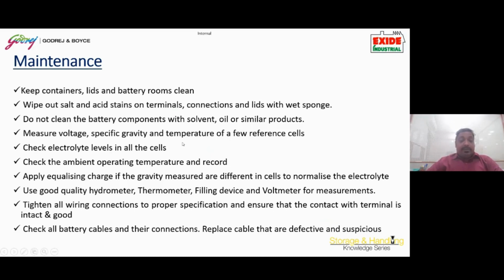The specific gravity, voltage and temperature of your reference cells should be measured periodically and noted down. The electrolyte level should be checked periodically during every charge-discharge cycle, and ambient temperature should be recorded, to assess the temperature of the battery. Equalizing charge should be applied. I normally recommend customers to do it at least once in a week, and if they can't do it once in a week, they must do it once in a month. And use a good quality hydrometer and thermometer.